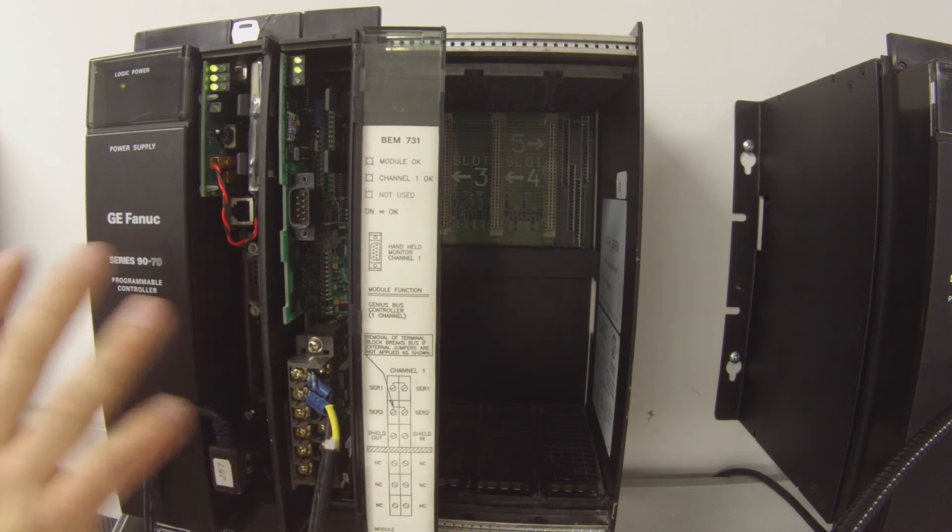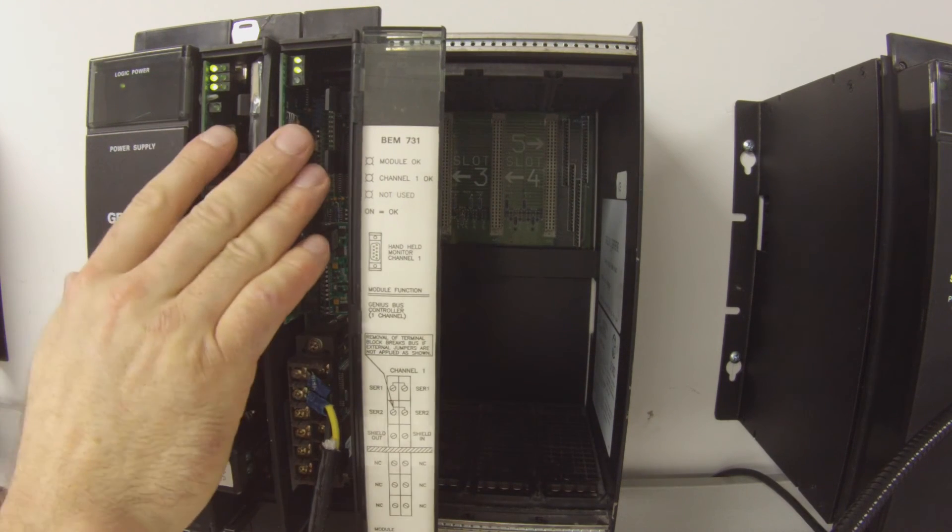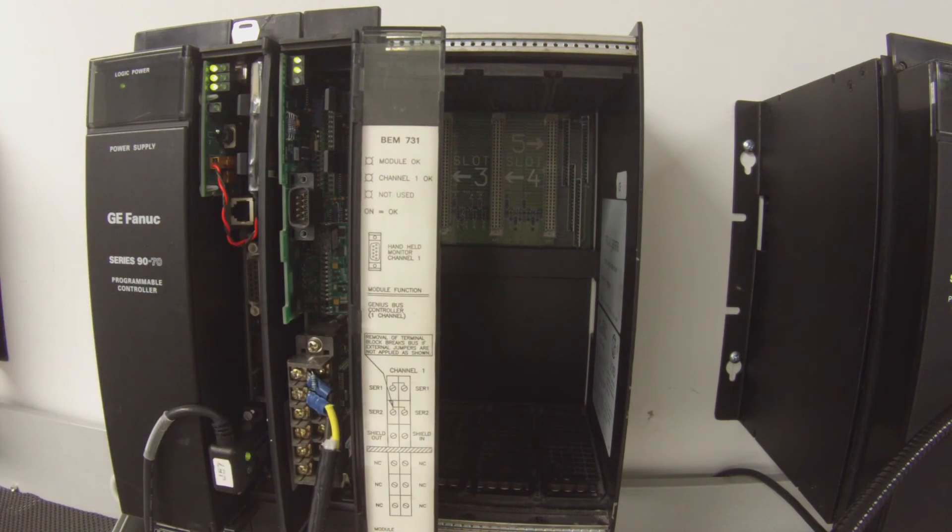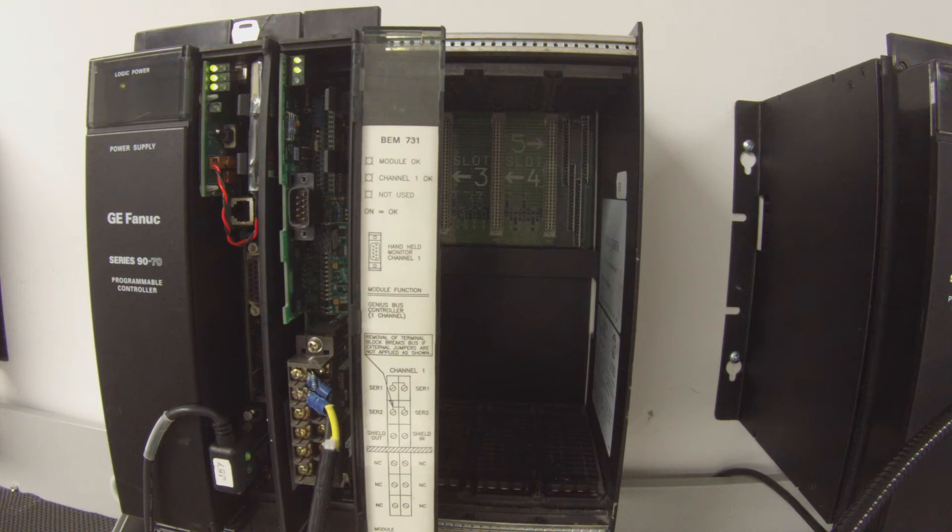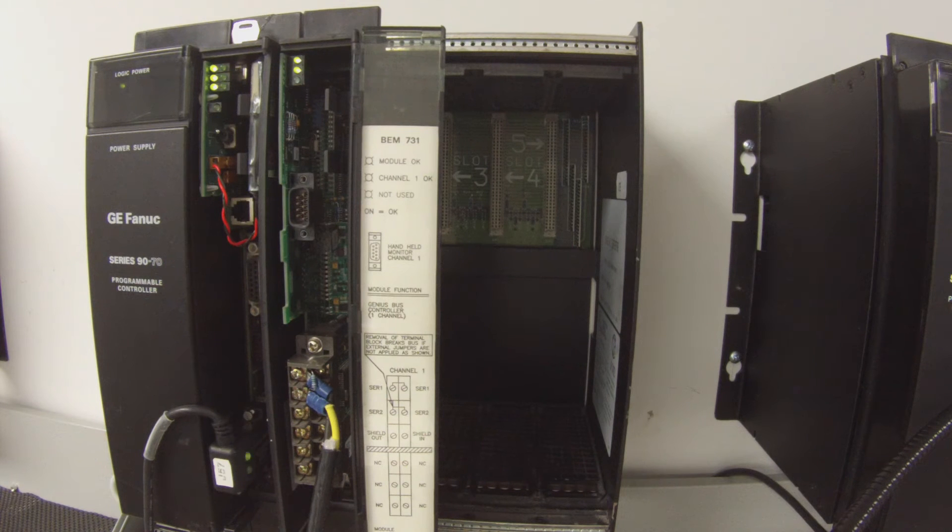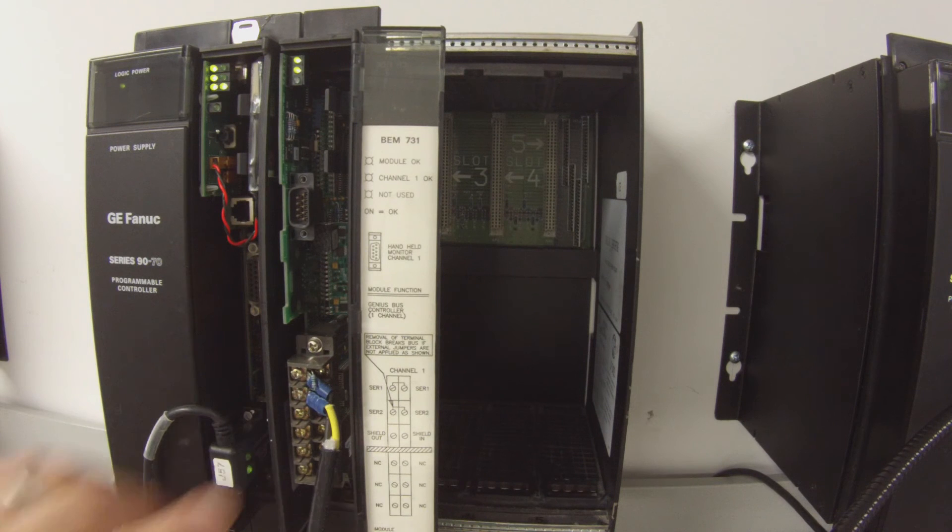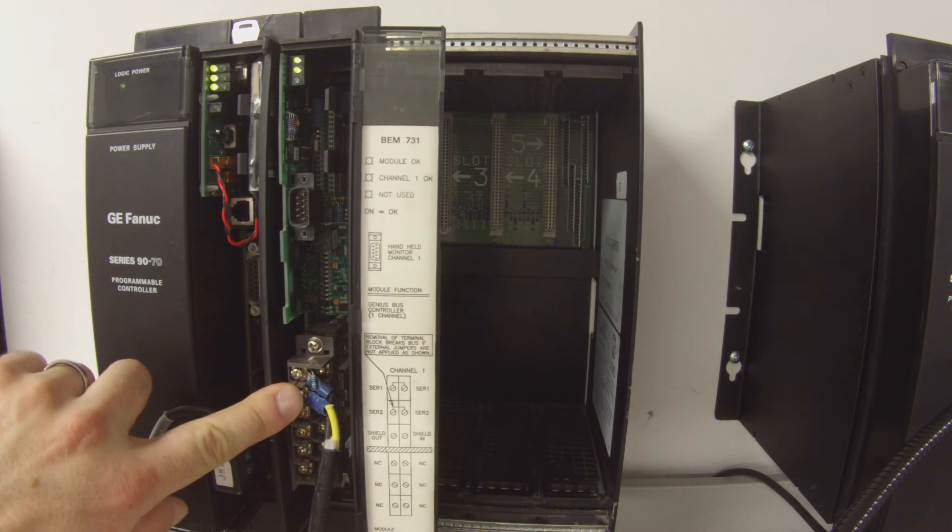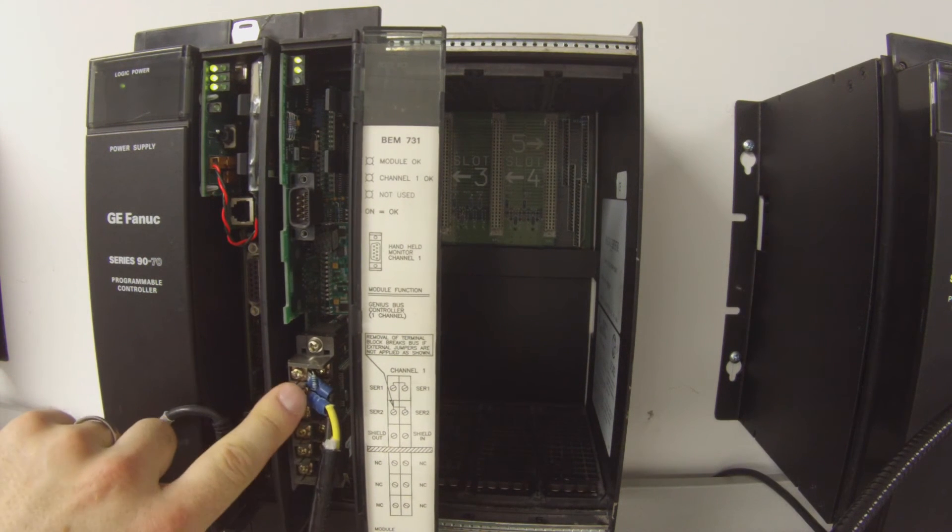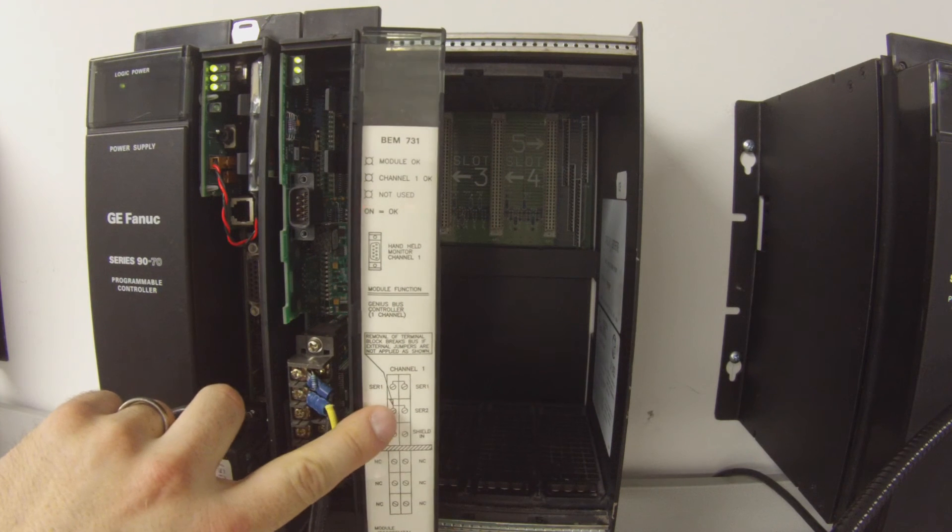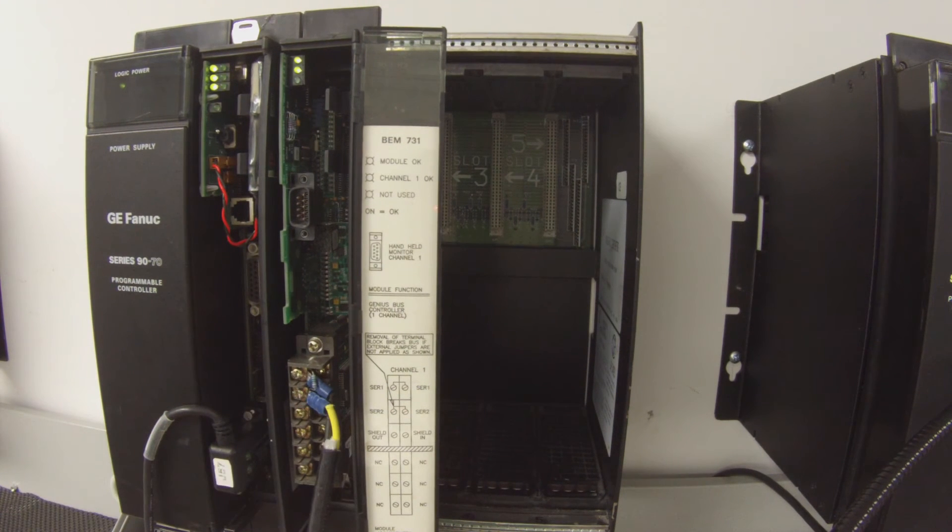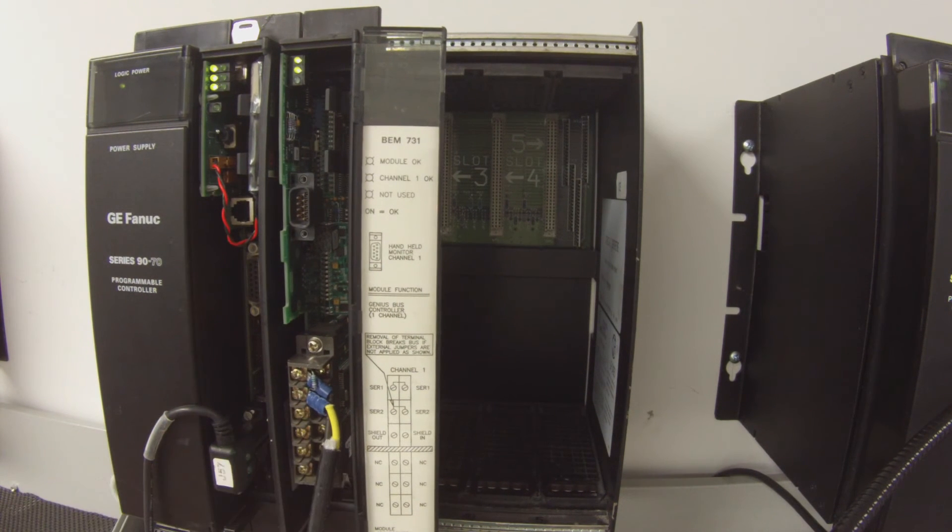So all those things match. And when I go into run mode, if the block is powered up and the block is at serial bus address number one, what I should get on the block is an IO enabled light on, which I do. So that means that I'm able to communicate to a genius block using this channel one here is very important. That's the number one thing that you want to be able to do with this BEM.